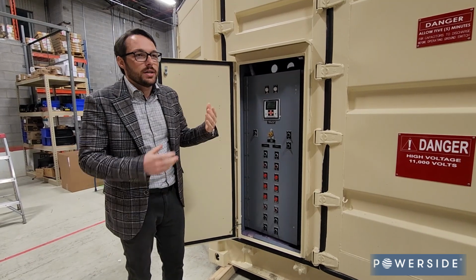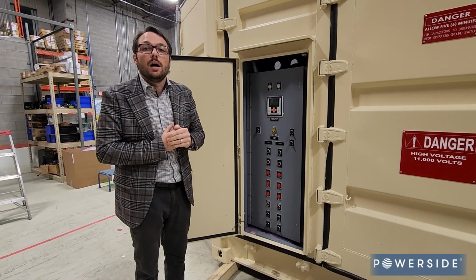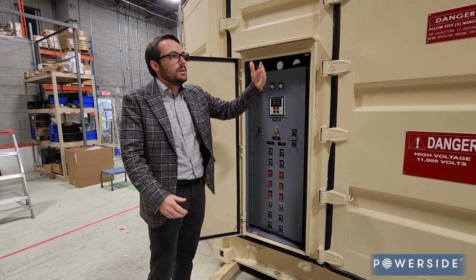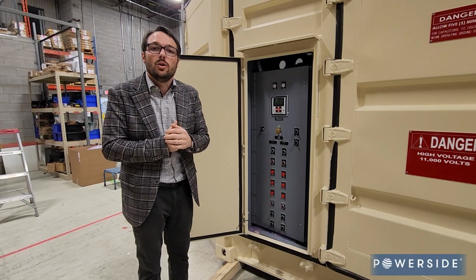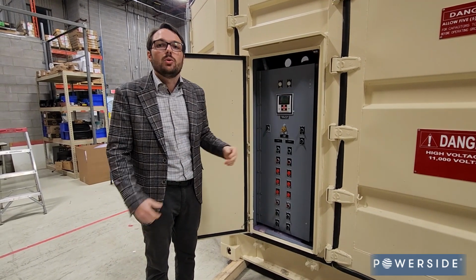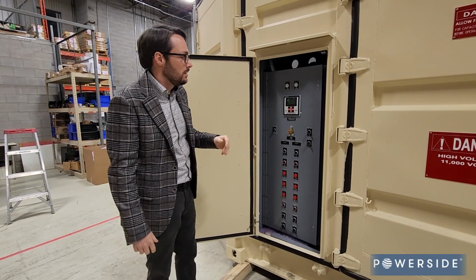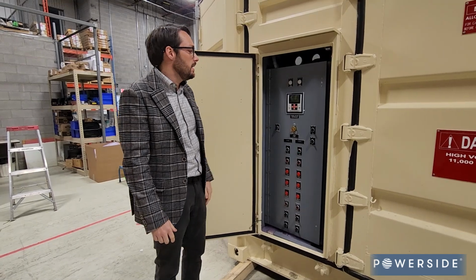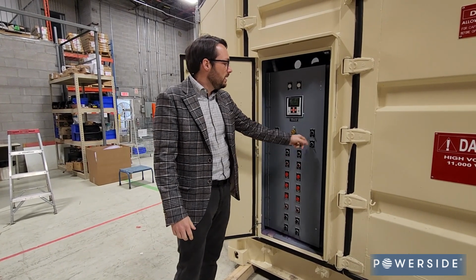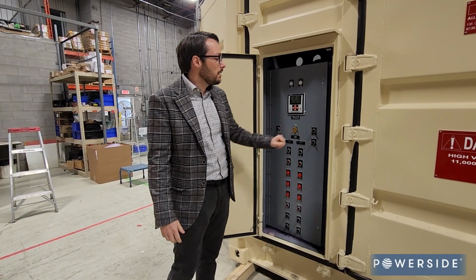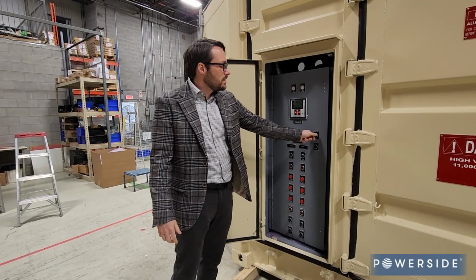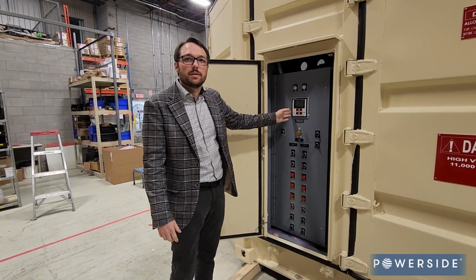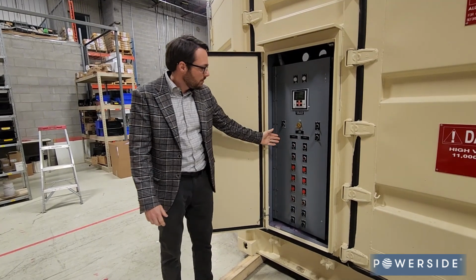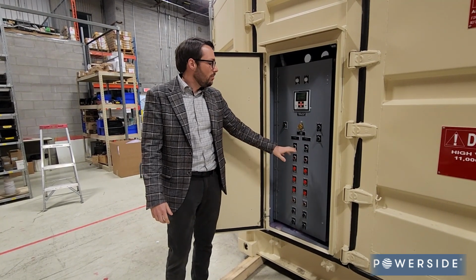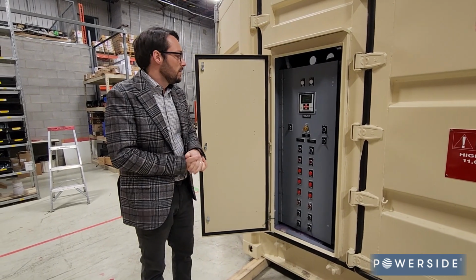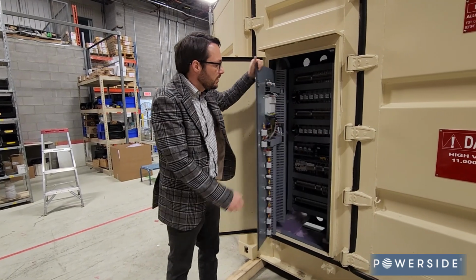This will be set up with a current transformer that is sensing the load upstream, and then the controller will close the various stages as the load changes and as the load requires more VARs to maintain the target power factor, which is pre-programmed internally here at 98%. Now, on all of our medium voltage banks, we have the ability to run them in manual mode and automatic mode. And so we can simply flip the switch here. Everything's running through our power factor relay control. Or in manual mode, I can select each individual stage, open and close the stages. And of course, these have timers that are built in back here.